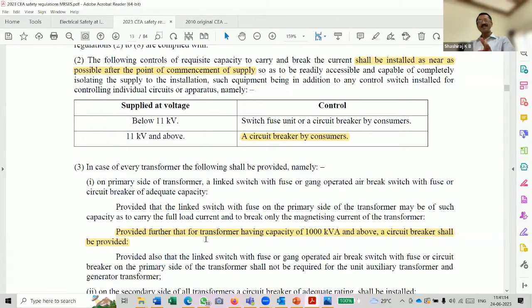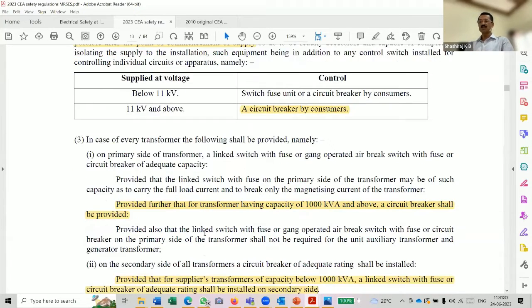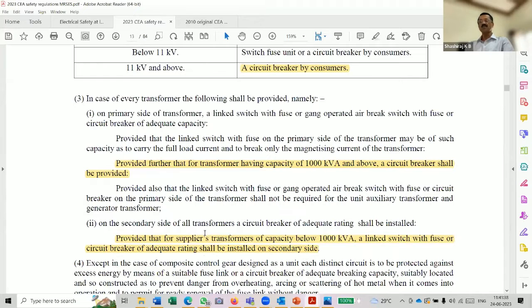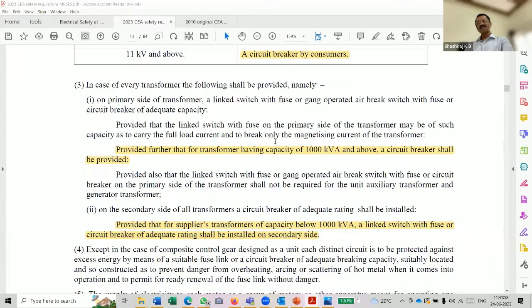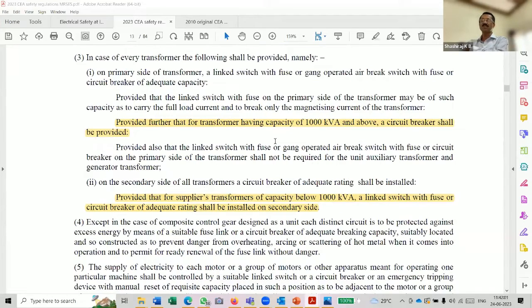Now, 37.2 specifically talks about consumers, so it is universal that as far as DISCOMs are concerned, the point of commencement of supply does not apply at all. The primary control does not apply. But when we come to 37.3, it does apply, and all stations of DISCOMs are required to have protection on the primary side for transformers of 1000 and above. But obviously, the DISCOMs have stations, and only around 2005 in the state of Karnataka, we were not inspecting the stations of the DISCOMs before provision of the drawings.